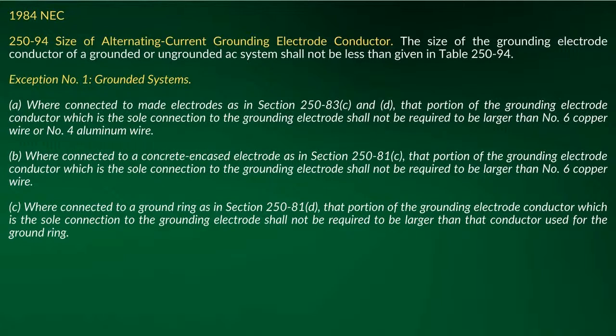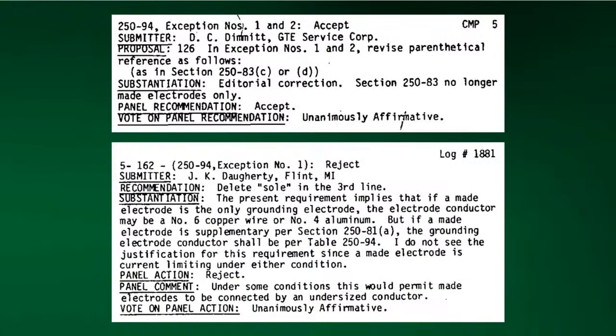So the other thing I'll point out one more time, it doesn't matter if I go to a ground rod, concrete encased electrode, ground ring, it still says shall not be required to be larger than. You see that? Right. In all 3 of them. Okay. Right. Now, look at this. This was exception 1 and 2. And they were doing editorial corrections when this took place, and they were talking about 250.83 no longer made electrodes only. So they unanimously voted that. Okay. Right. And they basically were saying we now have C and D, which is concrete encased electrodes and a ground ring. So there's no longer made electrodes just in that section, and that was voted unanimously affirmative.